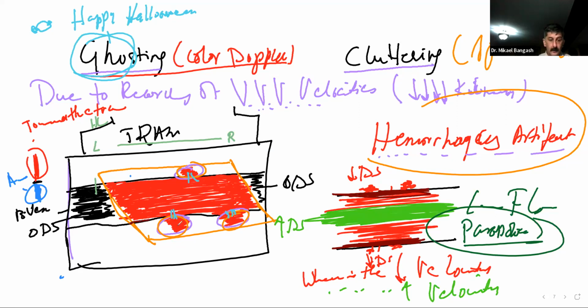So primarily we're getting rid of this. But if you keep on increasing your color Doppler, no, sorry, wall filter, of course there's going to be a limit. But what it will do is remove the low Doppler shift frequencies even within the vessel wall. So the vessel is actually going to look less filled out, because this area becomes blacked out.